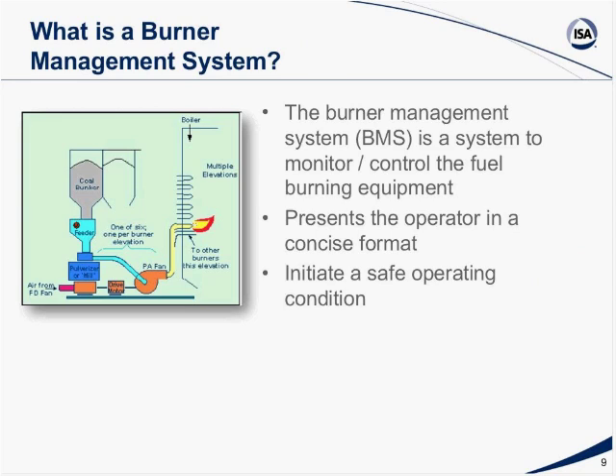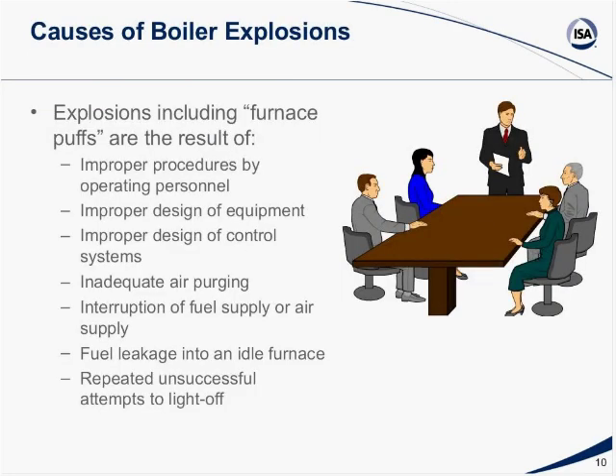The burner management system is a system that monitors and controls the fuel burning equipment. It presents the operator with information in a concise format and initiates safe operating conditions. Causes of explosions: there are many things that will cause an explosion, as I will address and discuss further on. One of the main reasons for explosions is operator error, but I will cover those in more detail in just a moment as I talk through these systems. That's improper procedures by operating personnel, improper design of equipment, improper design of the control system, inadequate air purging, interruption of fuel supply or air supply, or introducing them in an incorrect manner, so you'll end up with a fuel-rich mixture that will cause an explosion.